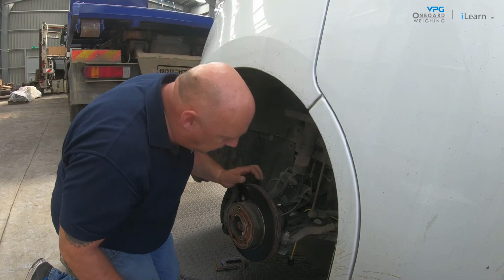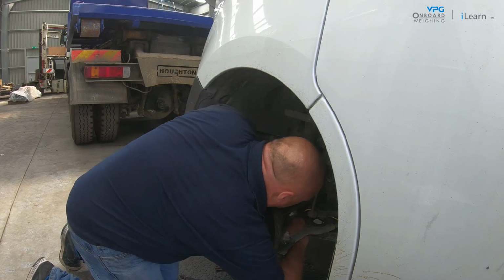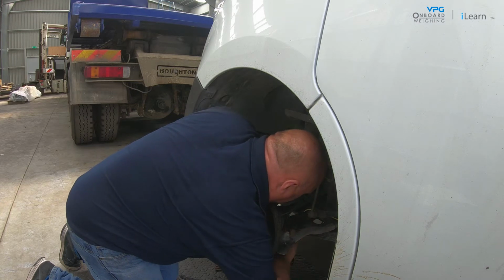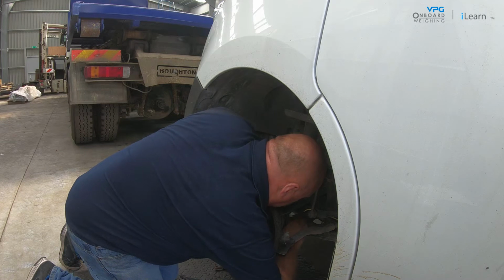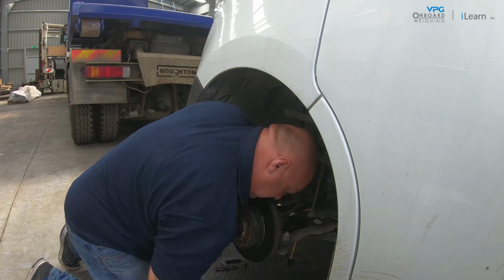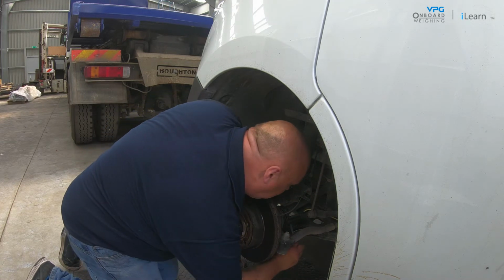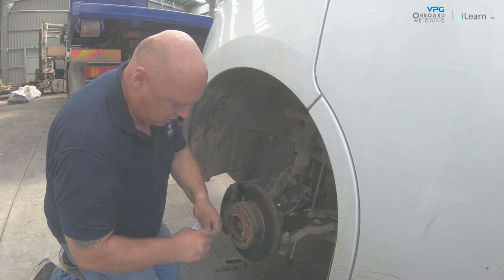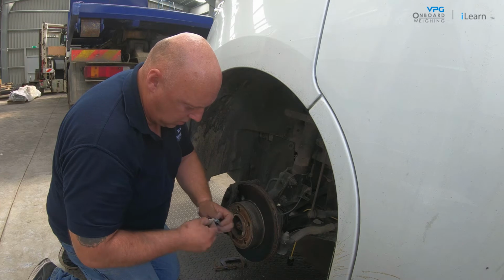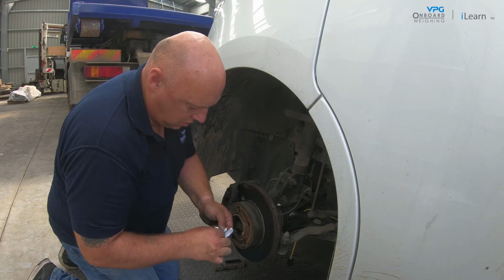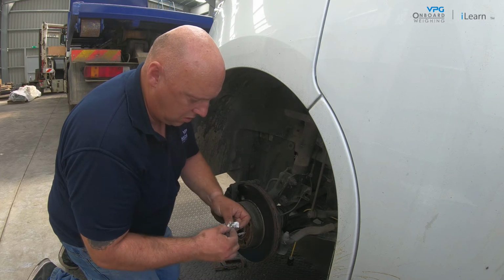First, the mounting surface must be prepared. Remove any dirt and debris at the position where you want to mount the transducer. Use Scotch-Brite and brake cleaner to clean the surface down to bare metal. And use alcohol wipes to finish cleaning the area and allow enough time for the cleaner to evaporate.